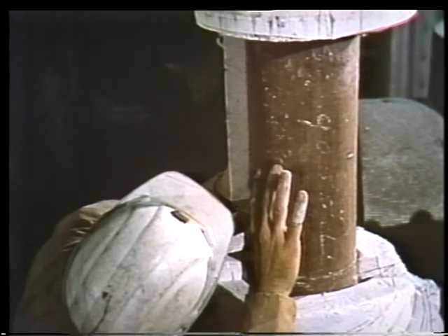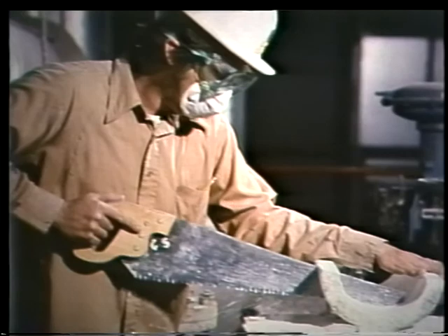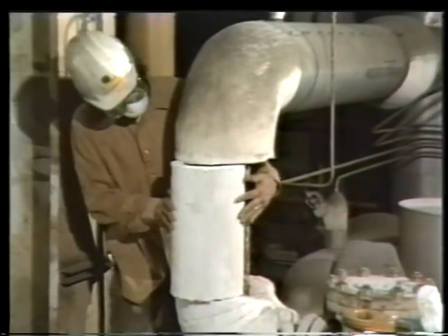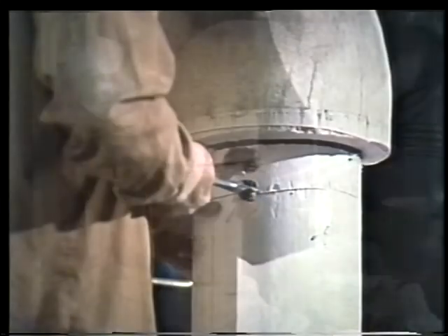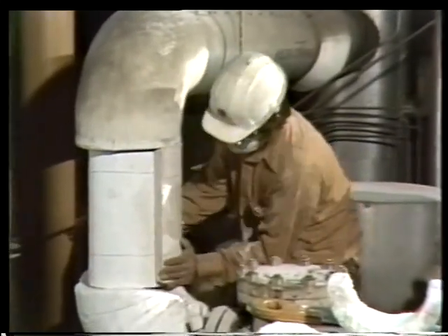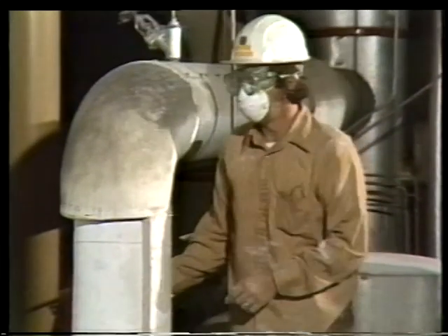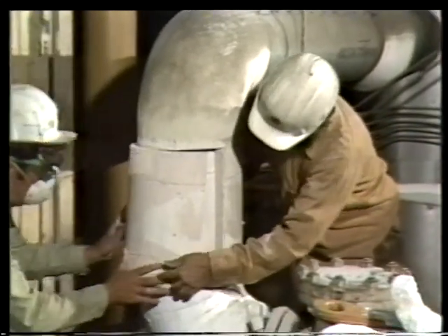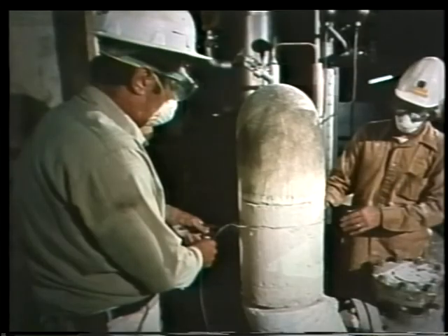The straight gap is measured so new pieces of insulation can be cut to fit. The new sections are cut with a standard ripsaw. The insulation is mounted on the pipe, and the wires are tightened, just as before, flush with the surface of the insulation. The outer layer is put on so the seams do not match up with those of the inner layer. This helps prevent concentrated heat losses through the cracks between halves. The insulation is then wired on in the normal manner.